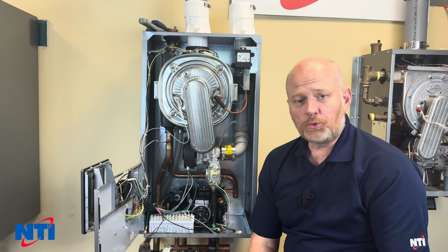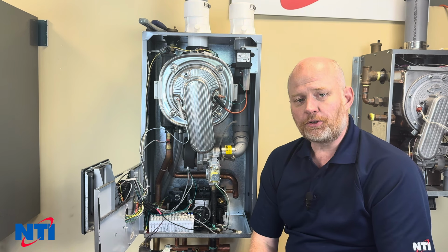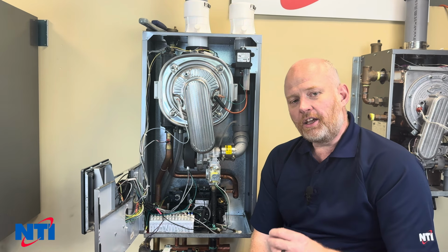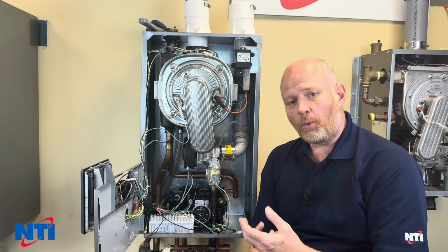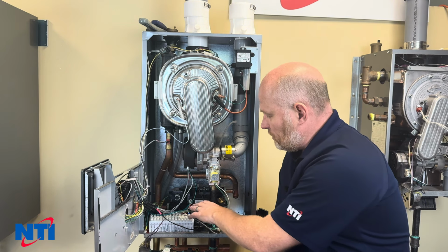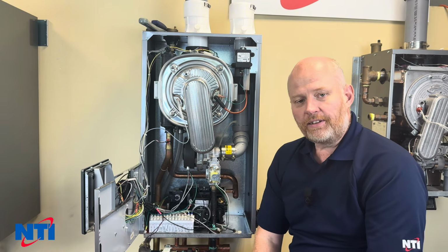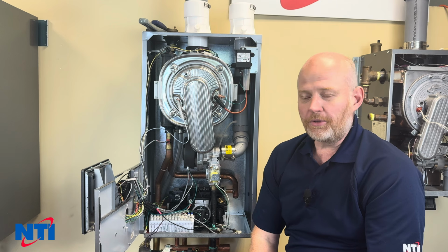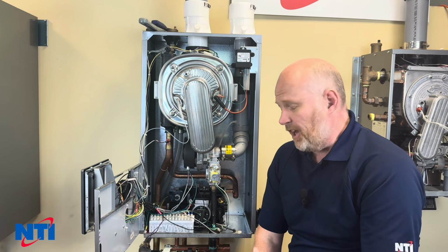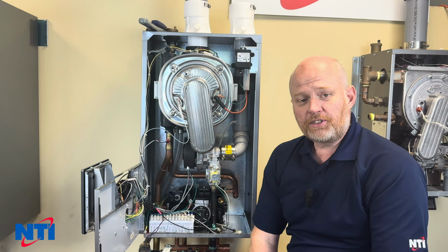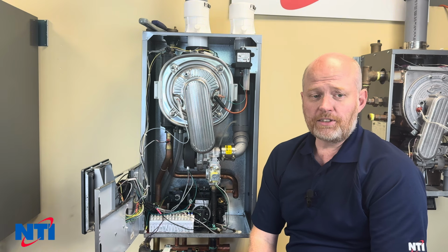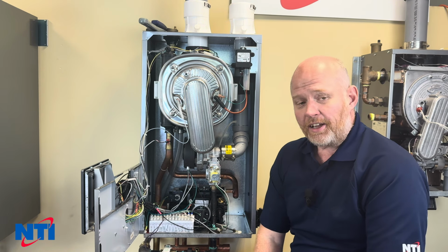You can, of course, introduce water into the boiler first. The main concern is that when you fill the domestic side, you want to do it slowly and do it with the hot water taps open. Potentially filling it too fast can destroy the flow switch in the boiler, creating a problem that you will have to fix. If for some reason you have to replace the flow sensor, see our video on replacing the flow sensor. And other than that, I thank you for watching.